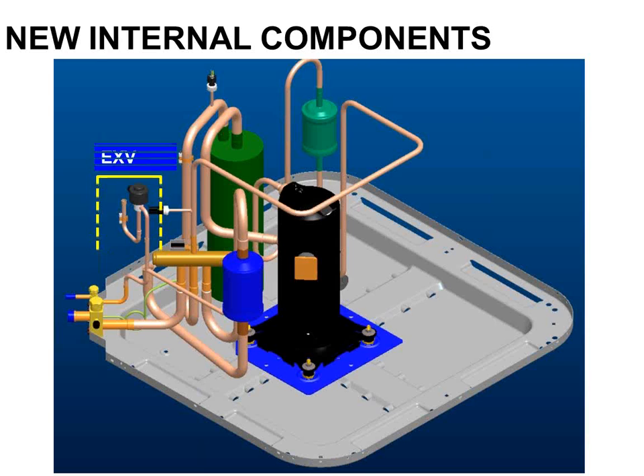Because you have an inverter, and I'm going to explain what an inverter does in a second, it operates at different frequencies, and one of those frequencies could have a harmonic with the building. So in some cases, you may want to put a muffler on the refrigerant line so those frequencies don't propagate their way through the building structure. There's an EXV. That's my expansion valve that meters the refrigerant in the heating mode as it goes into the outdoor coil, which is now my evaporator coil.